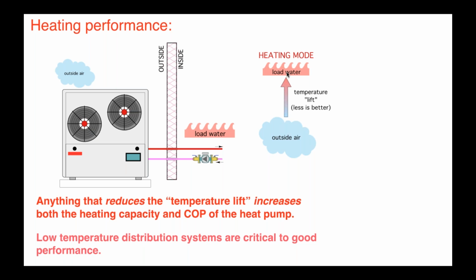Anything that brings these two temperatures closer together, in other words, anything that reduces the temperature lift, is beneficial. It's going to give you higher heating capacity and higher coefficient of performance, and vice versa. Anything that pushes them farther apart is going to lower the performance of the heat pump.